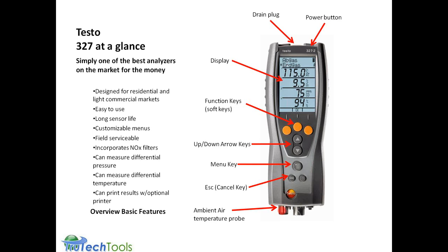At the very bottom, in a little cage, is an ambient air temperature probe. This is a reference point for the meter to tell it what the surrounding temperature of the air is before combustion, so it knows how to make an efficiency calculation. But you can also remove this cage and put in an optional probe, which could be a clamp probe or a bead type probe, various types of probes that are used for measuring air temperature, surface temperature, and that kind of thing. That's where you get the differential temperature measurement out. But it comes standard with this little air temperature probe in a cage.